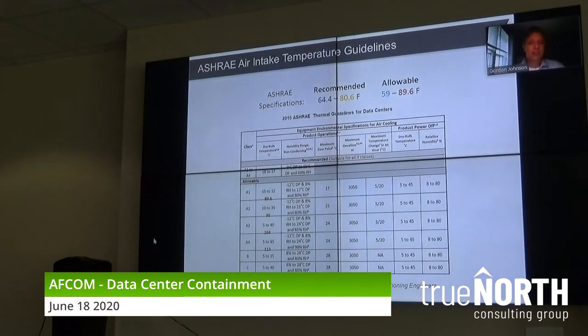So for instance, if you have A2 type equipment, if a CRAC fails and you've got to fix that CRAC unit, that's not a big deal. If you go above 80.6, maybe you go to 88 degrees, maybe you go to 92 degrees, it sounds bad. You're going to get a lot of alarms. You're not breaking your warranty. You're not shortening the life of your equipment. You're in an allowable range. You just can't run your data center that way 24/7.